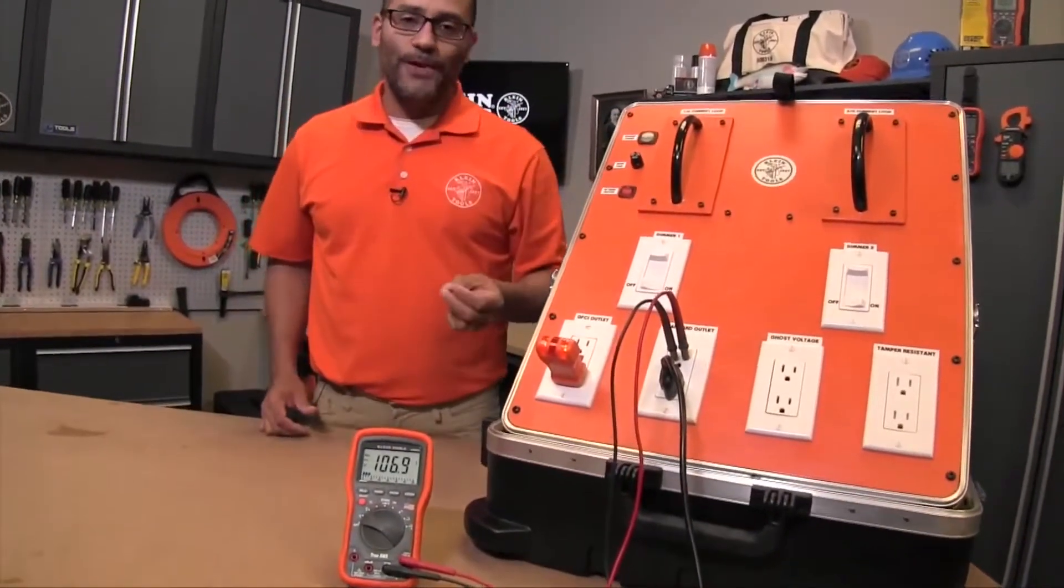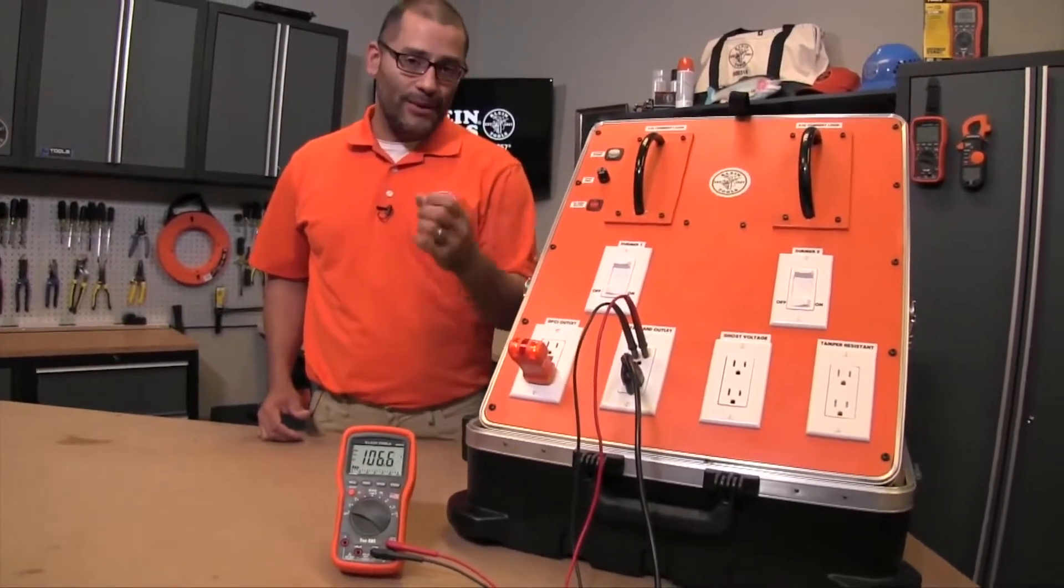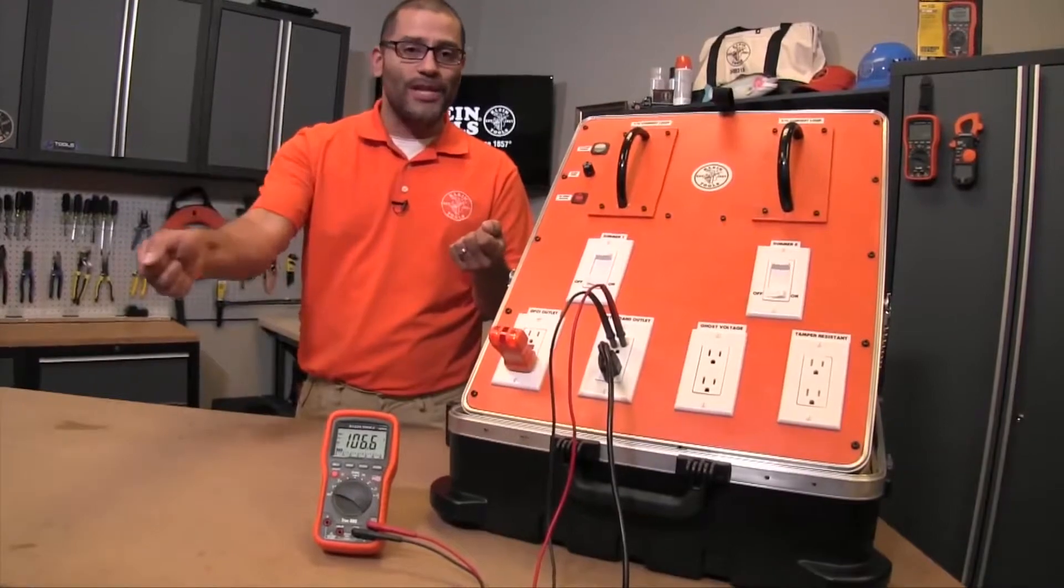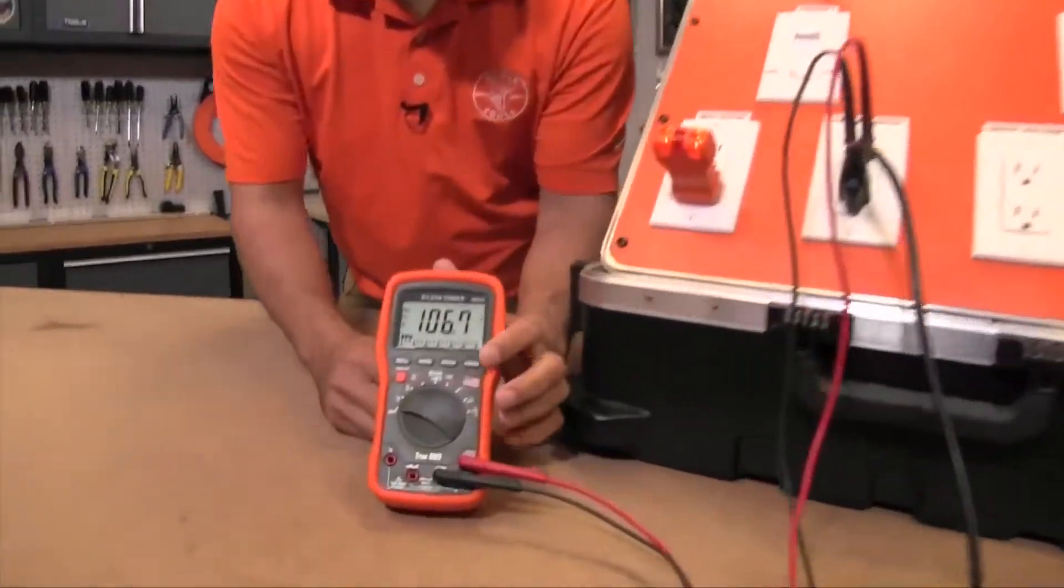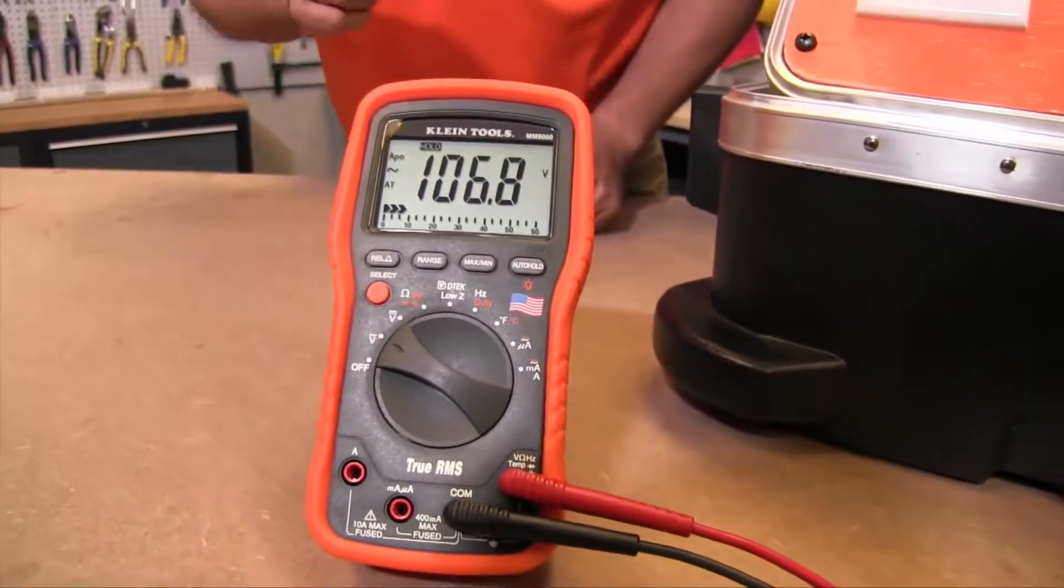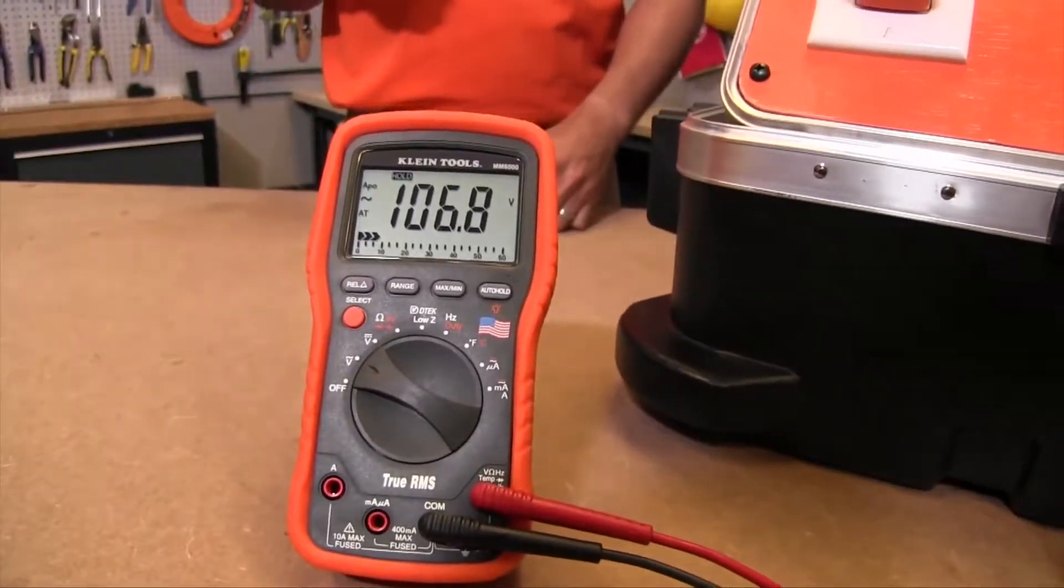So with the hold feature, the hold is designed to capture that reading that you see on the screen. So you're taking your measurement, you've got the meter in front of you, you hit the hold button, so right here you see hold pops up and it locks in the voltage at one hundred and six point eight volts.